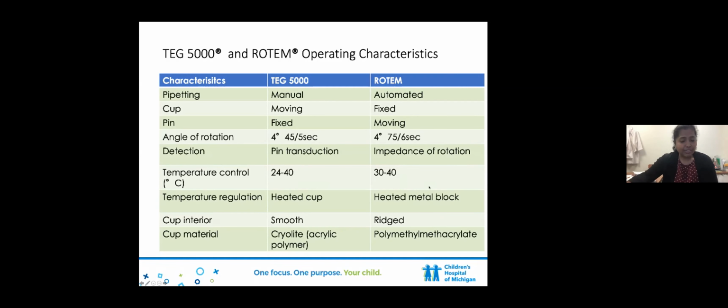So you can actually study the process of coagulation at a more physiologic temperature, but also, with more technology and cooling protocols taking place now, if you wanted to study coagulation in a baby that's undergoing cooling, you can actually bring down the temperature of your TEG or the ROTEM to the temperature that the baby's at and study coagulation at that temperature.